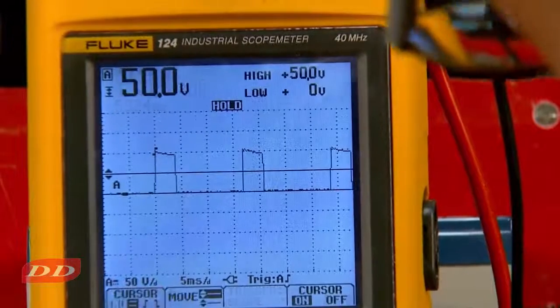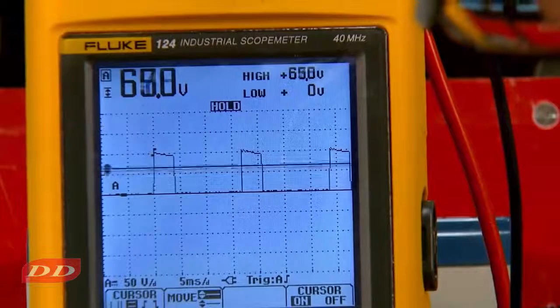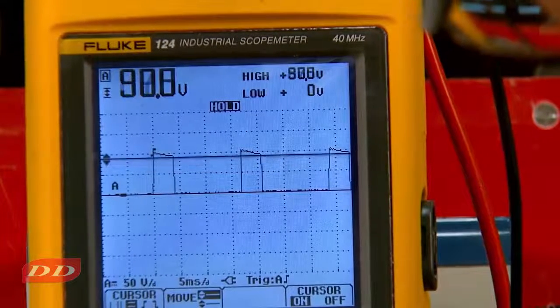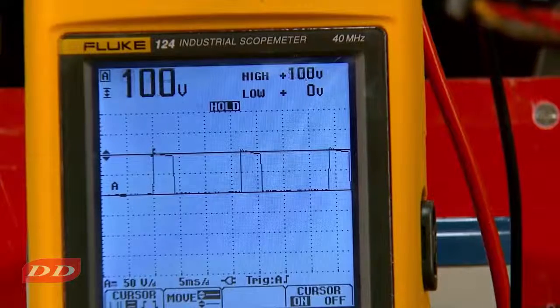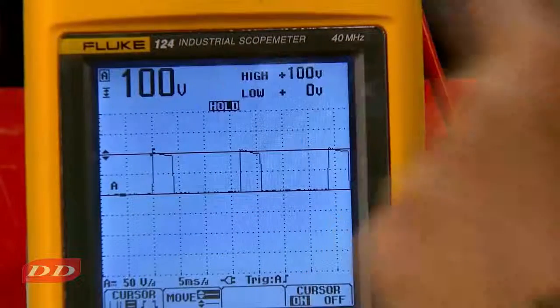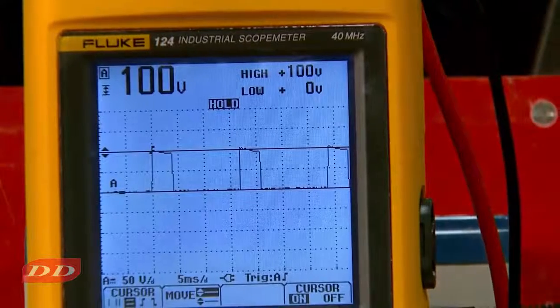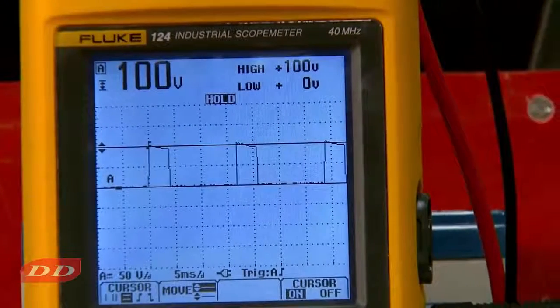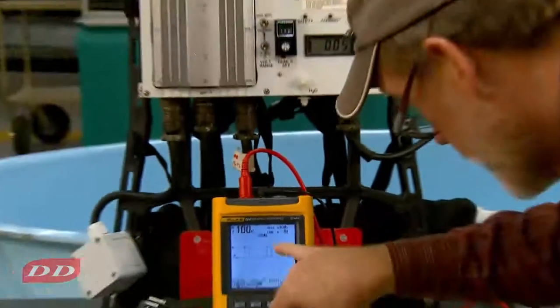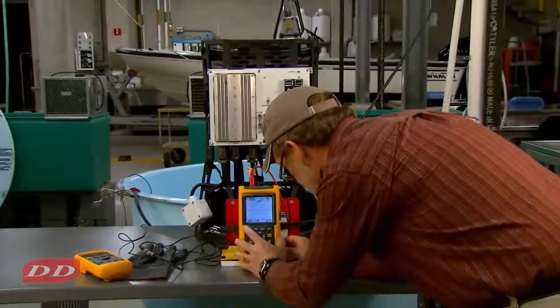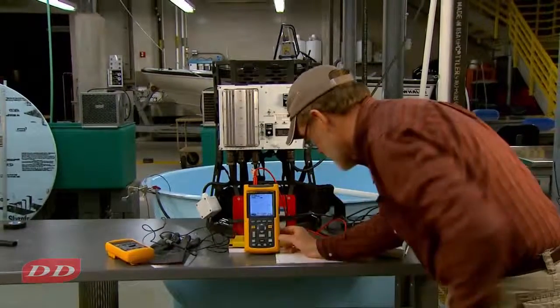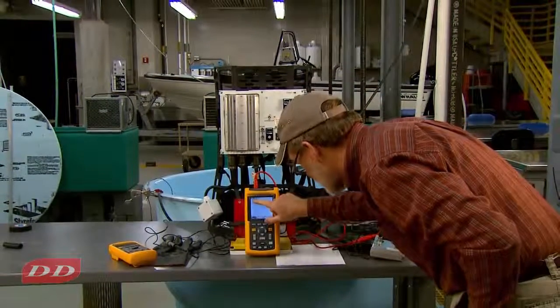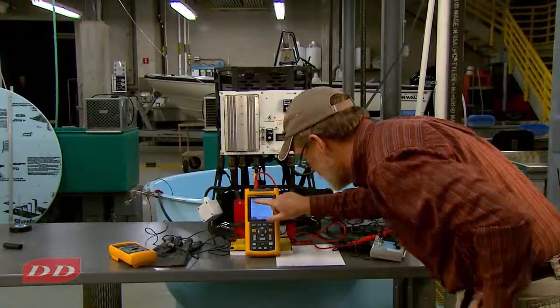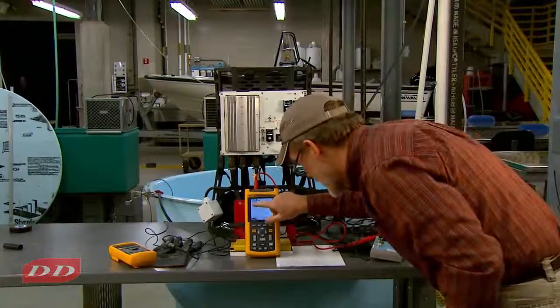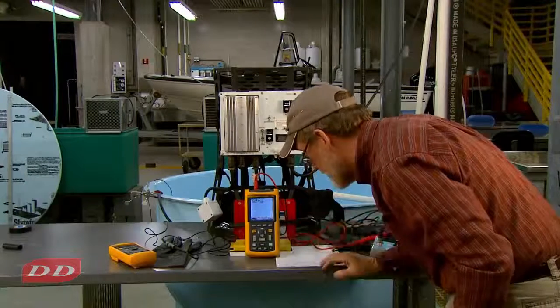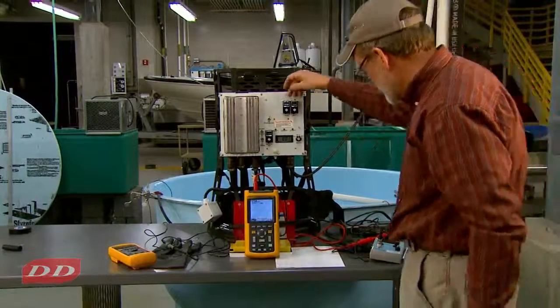We'll do the cursors one more time here, and so about, again, nearly 100 volts. So that's what we put on. There's a couple other things that the scope meter does, a couple other measures we have up here. And when I turn the cursors off, we see that we have a reading for duty cycle, 23.4%, and a frequency reading of 59.24.